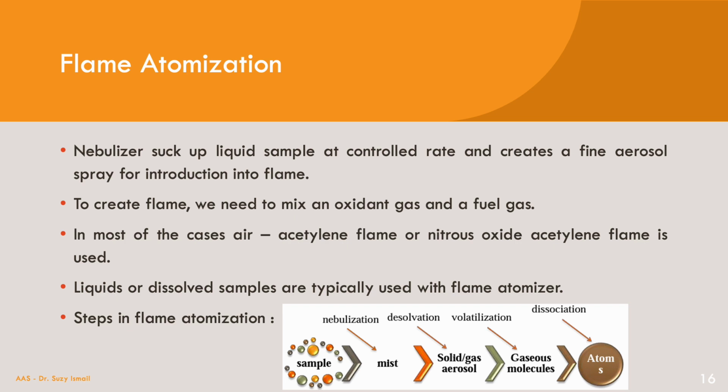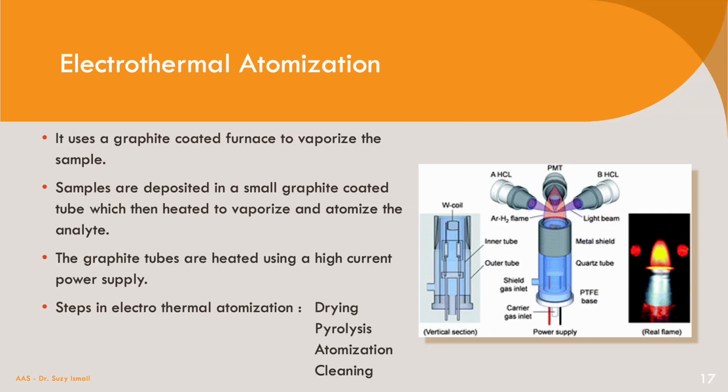From the molecules it becomes the atoms. This is what atomization is meant for. From your sample it becomes compounds and then molecules, and from those molecules it turns into atoms. So this is under flame atomization. And for electrothermal atomization, you undergo the process of drying, pyrolysis, atomization, and cleaning in the thermal atomization process.